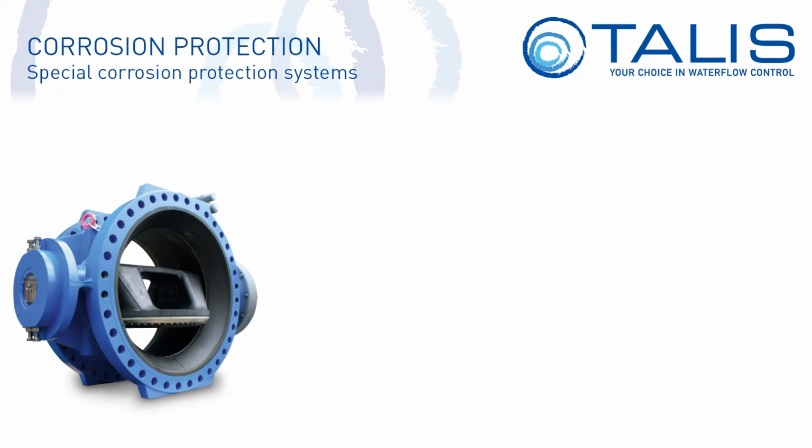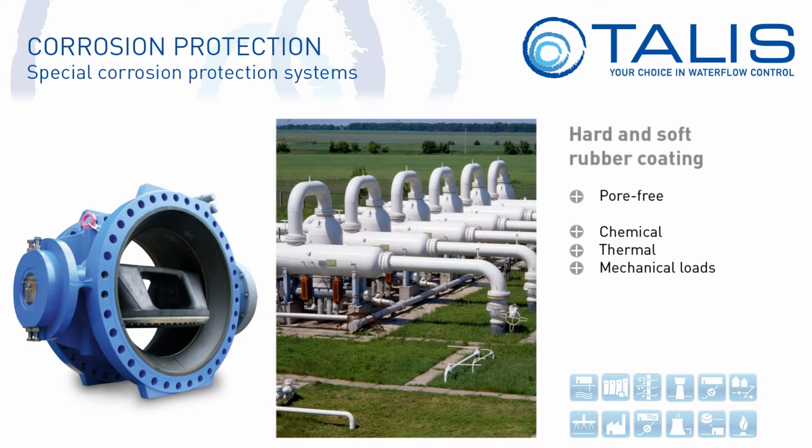With a layer thickness between 3 and 6 millimeters, rubberizing is by far our thickest coating. Rubber coatings are pore-free and are resistant to chemical, thermal, and mechanical loads. Whether a hard or soft rubber coating is chosen depends on the mechanical strength and chemical resistance requirements. Rubber coatings are chosen for valve body linings, which are exposed to aggressive fluids such as seawater.